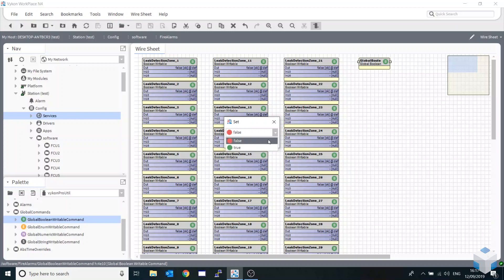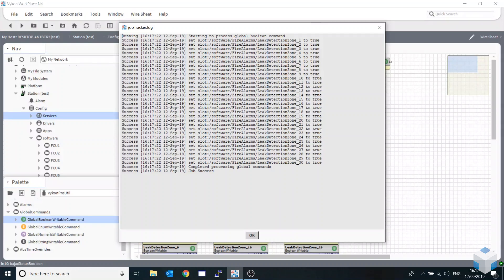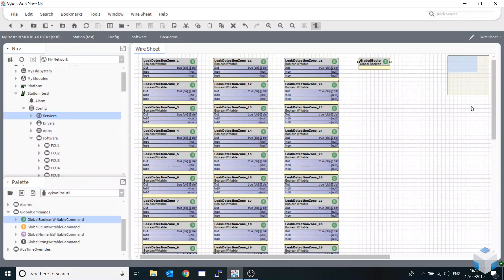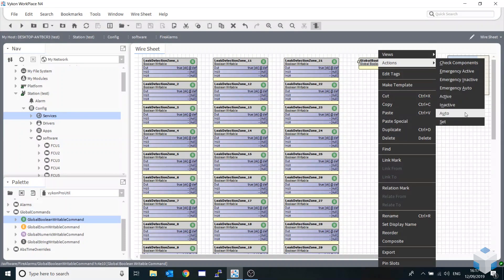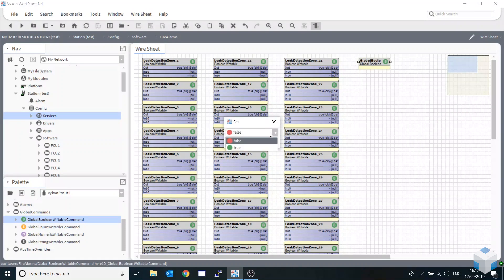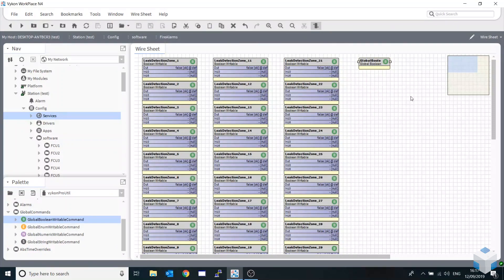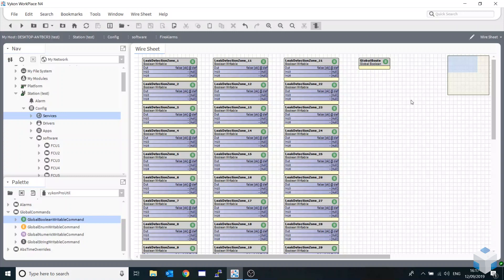Job tracker runs through and gives me a confirmation that it's actually run through and done the whole job. Hit OK, and as you can see all my boolean writeables have now gone to true. We're going to do that in reverse - action set false, confirmation, and again it's gone back and put our points back into a false state. So that's the global commands. Next part of our video we'll be looking at adding alarms on mass.